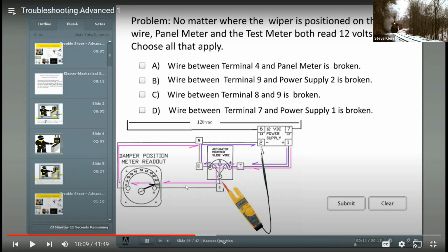But this time we've got our meter set up, so our meter is tied in. The negative goes to terminal 2. The power comes in off of 1 to 7 like it's supposed to. The power is supposed to go across that horseshoe portion, but it's actually coming out terminal 4 on the meter. We're reading our 12 volts there on the meter. So what would be missing to keep it from getting back to 2?